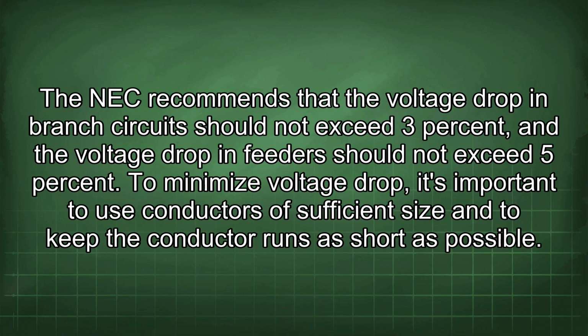The NEC recommends that the voltage drop in branch circuits should not exceed 3%, and the voltage drop in feeders should not exceed 5%. To minimize voltage drop, it's important to use conductors of sufficient size and to keep the conductor runs as short as possible.